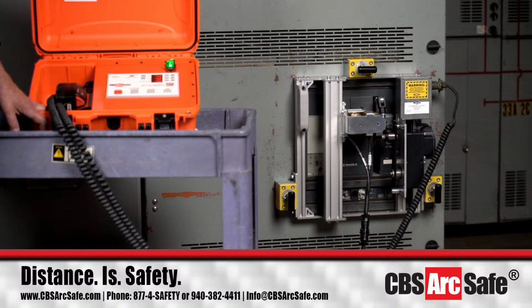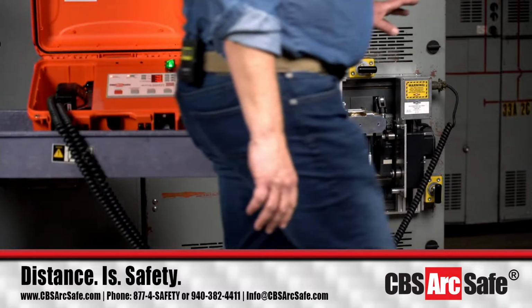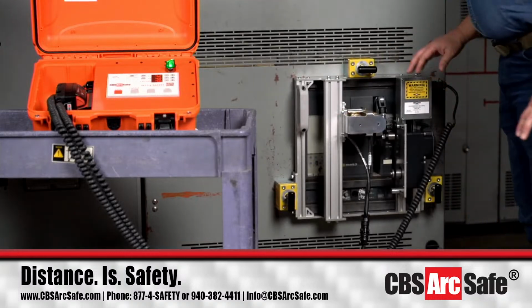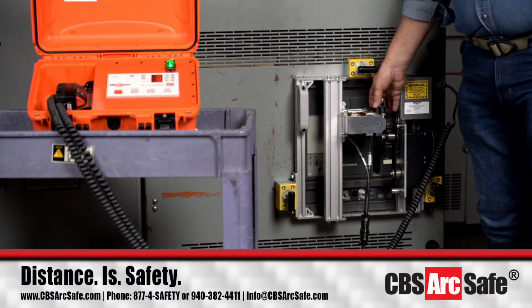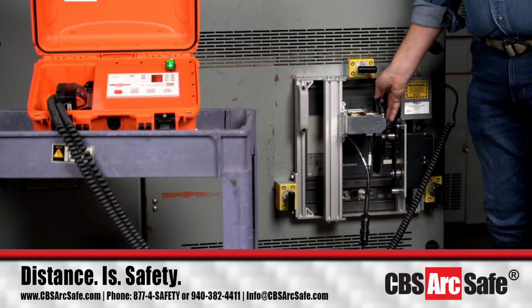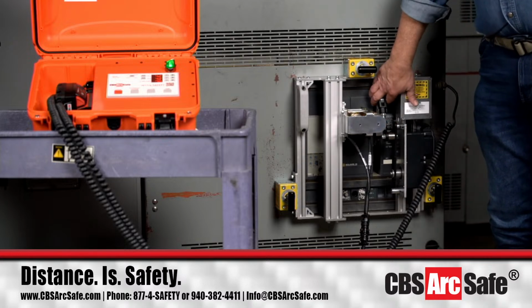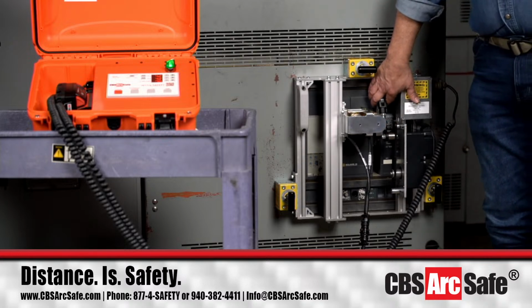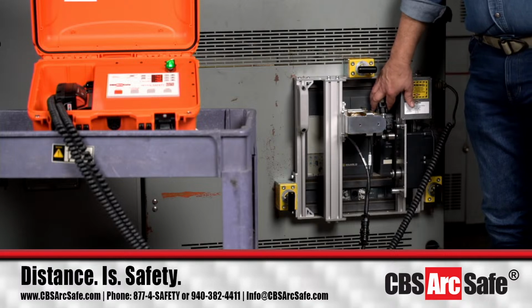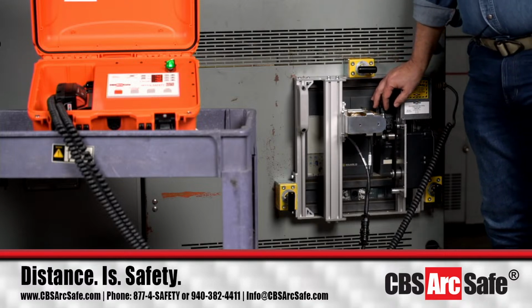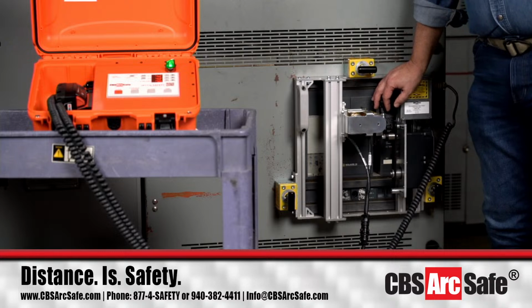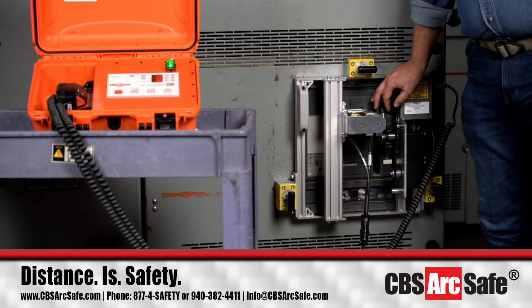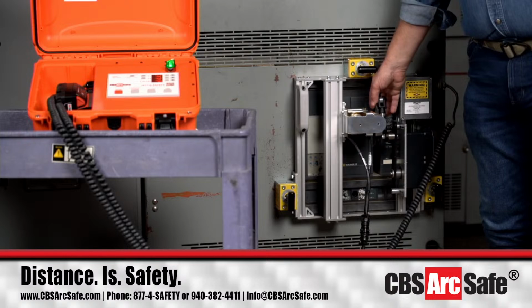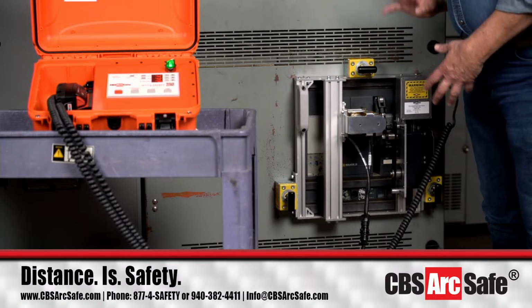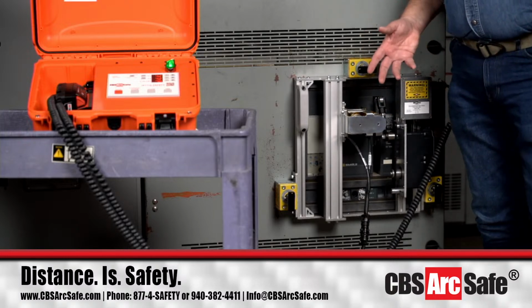Is that right, Kyle? Sure, it's MTZ. So the handle is one thing to understand: if you had an MP, an NW, and an MTZ, these handle styles will change. I could use this same RSA, but you'd have to have different handle adapters for that if you had those in your facility. If you were updating your breakers from NWs to MTZs, doing a modernization, you're just going to need a different handle adapter, because everything else has stayed in the same place as far as the face of the breaker goes.